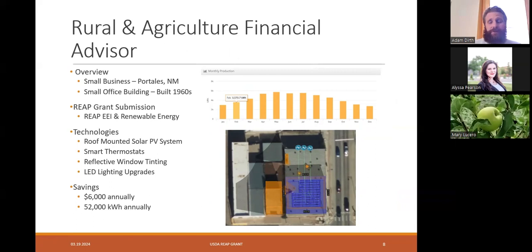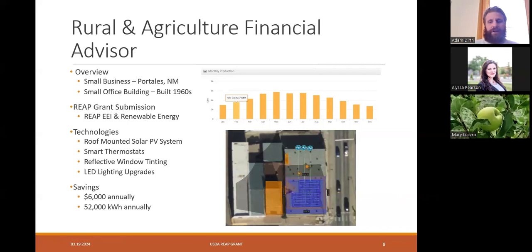This financial and insurance provider uses the building as an auto shop in the back and office space in the front. They want to make the space more energy efficient and comfortable for their workers and clients, and plan on expanding building occupancy in the future. We conducted an energy audit, created a building energy model, and used the data to design a solar PV system that eliminated 90% of their utility bill. This project is an excellent example of prioritizing energy efficiency before installing a solar PV system — using less energy allows you to install a smaller PV system.